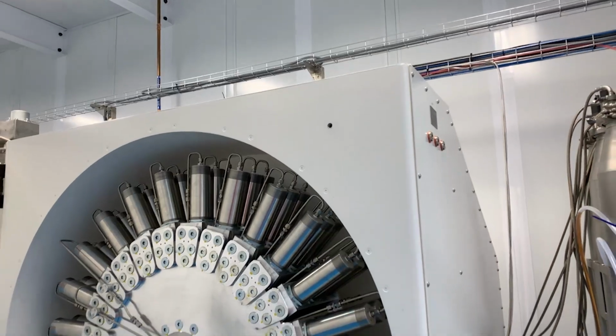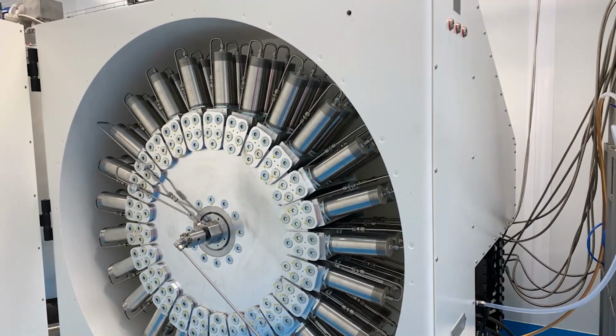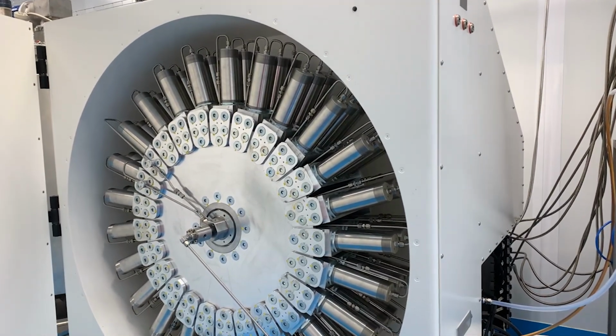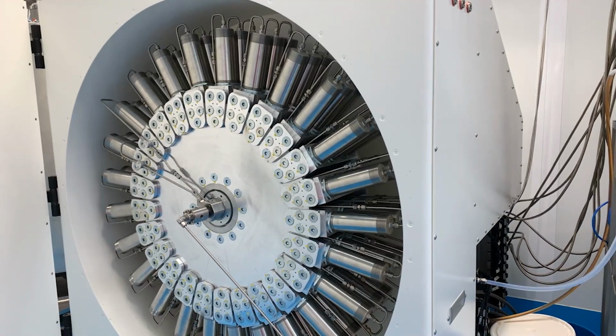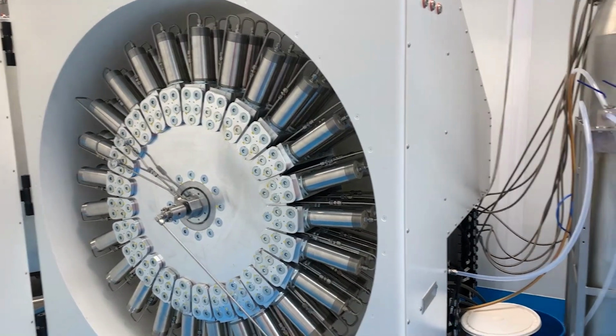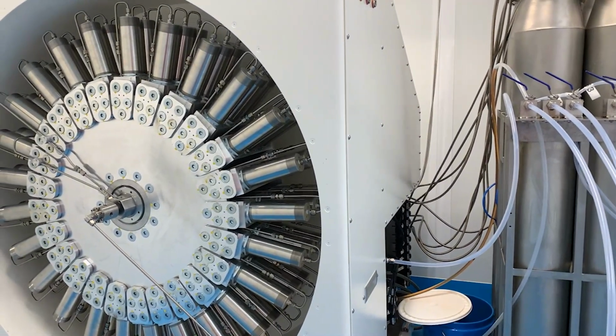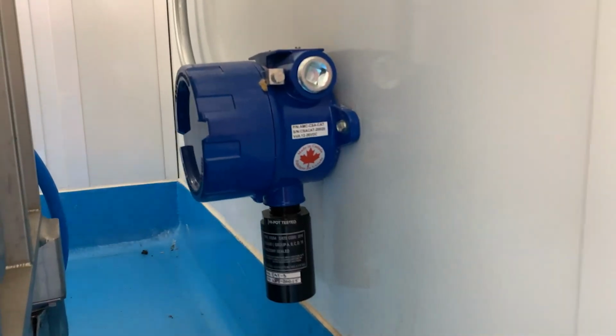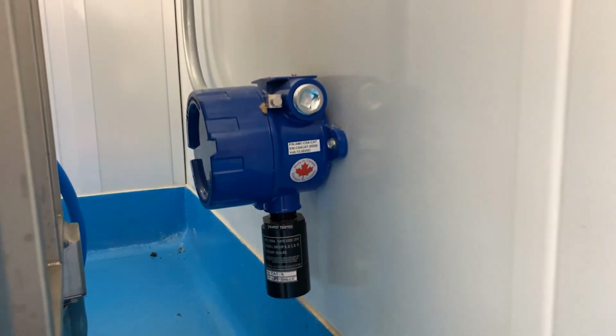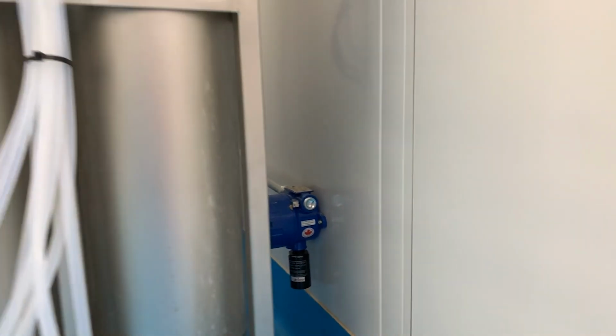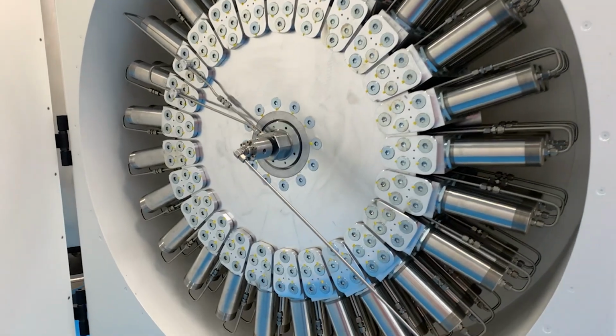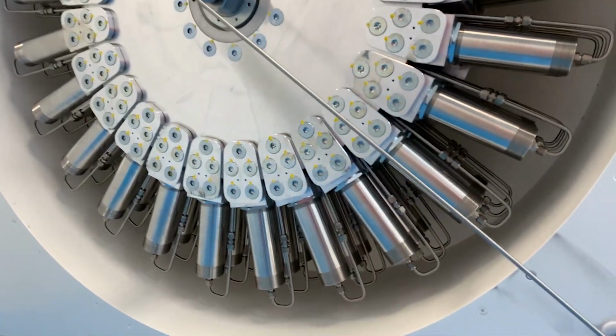Of course, during operation, the door is closed. The room is closed, and no operator needs to be in this room. The machine is controlled by the control cabinet outside, operating without human supervision. There's another gas sensor in this room, in case it's required. This is a closed-loop system. No solvent is coming out from the system while it's operating.